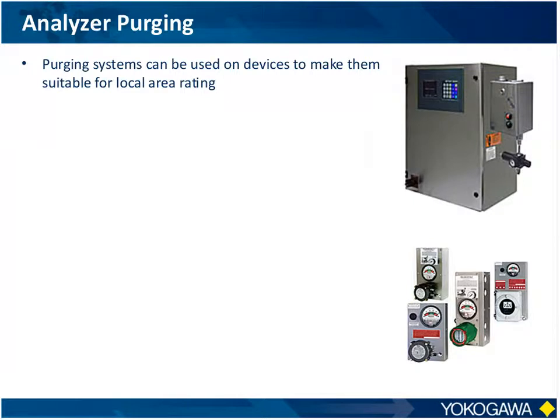You can actually mount the analyzer inside a box where you bring in known safe air, perhaps instrument air or plant nitrogen, and you keep a constant flow in there, so there's no possibility for leaks or accumulation of a hazardous gas inside of it to cause a problem.